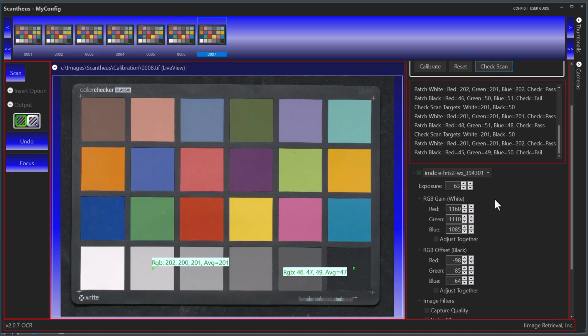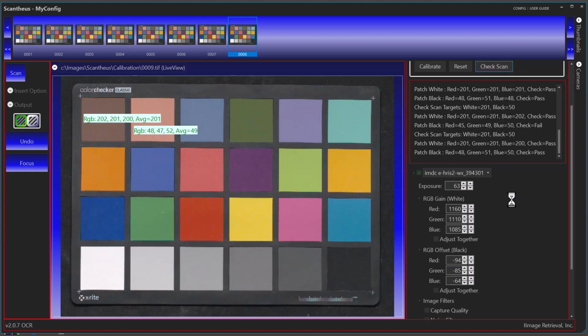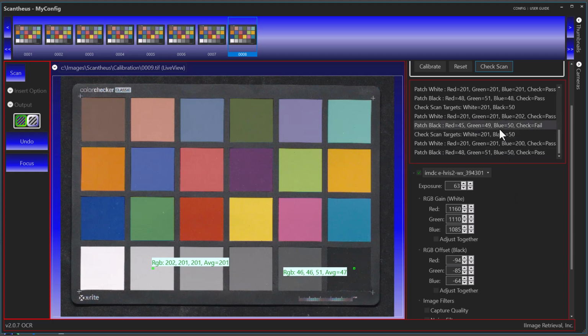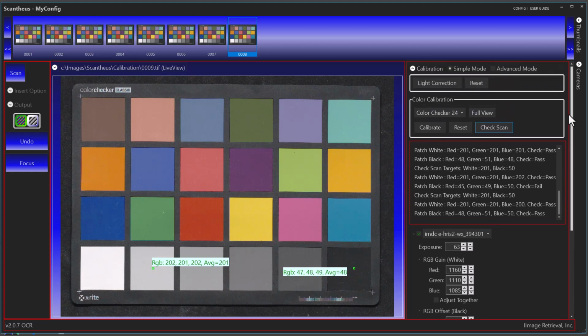If you notice, the black patch started failing on my check scans, and that's because I adjusted the gain down in order to get the gray patch in line. Well, that affects all the colors, so I had to go back to offset and bump it up in order to get it back into spec. But now both patches are looking good, and I have a calibrated scanner. Now again, that step I did there at the end, manually adjusting it, that's optional if you want to get zeroed in. If not, otherwise you're calibrated.